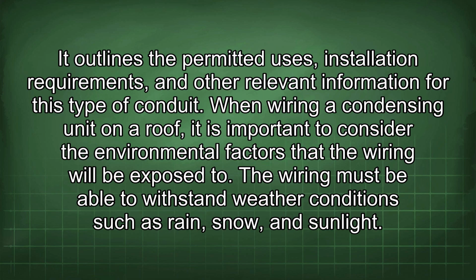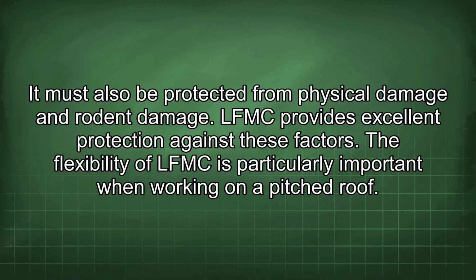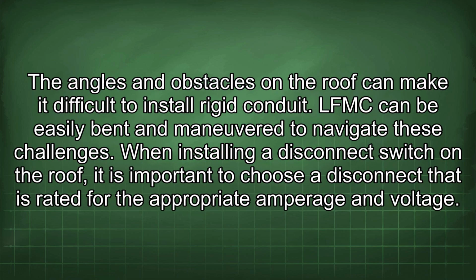When wiring a condensing unit on a roof, it is important to consider the environmental factors that the wiring will be exposed to. The wiring must be able to withstand weather conditions such as rain, snow, and sunlight. It must also be protected from physical damage and rodent damage. LFMC provides excellent protection against these factors. The flexibility of LFMC is particularly important when working on a pitched roof. The angles and obstacles on the roof can make it difficult to install rigid conduit. LFMC can be easily bent and maneuvered to navigate these challenges.